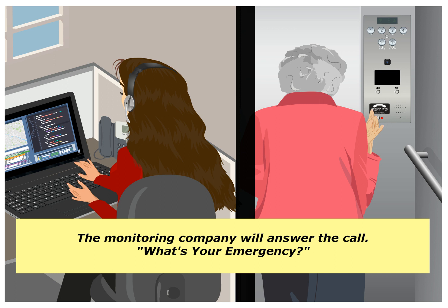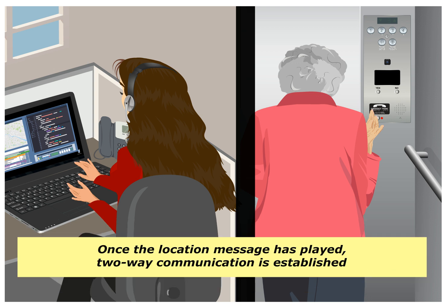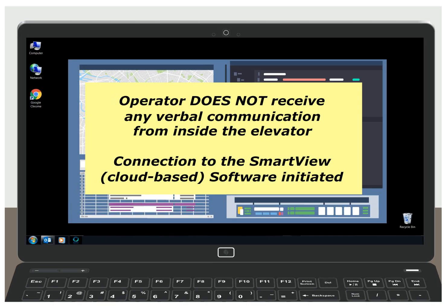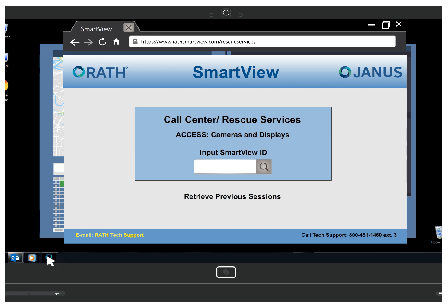The monitoring company answers the call: "What's your emergency?" The pre-recorded location message, which includes a unique ID number, plays twice for both parties: "Highland Hotel, Building A, Elevator 3, SmartView ID 12345." Once the location message has played, two-way communication is established and the call progress LED will flash. Since the monitoring company does not receive any verbal communication from inside the elevator, they will open a link on their computer to the SmartView cloud-based software.